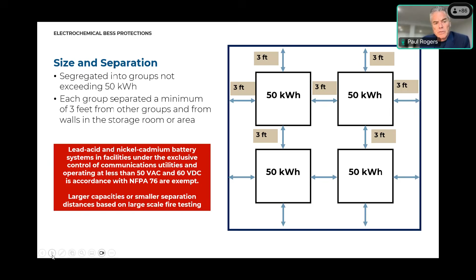But if you're going to stay within the guidelines and keep at 50 kilowatt hours, you have to stay 3 feet in all areas. It could even be further than 3 feet if there's a maintenance area, and the National Electric Code actually drives that. So you could see things as far as maybe 4 feet, but that's only because it's based on the National Electric Code for maintenance of these things. So there could be things in there that you have to take a look at. You can go into the next room.